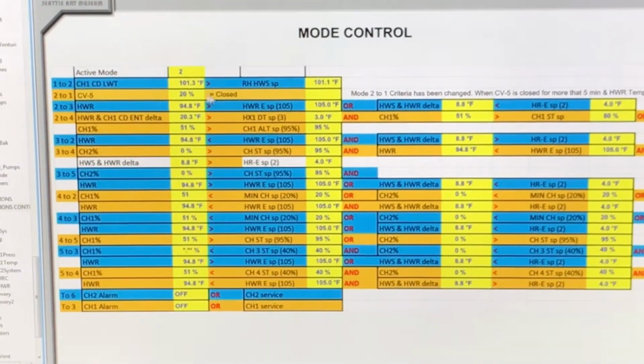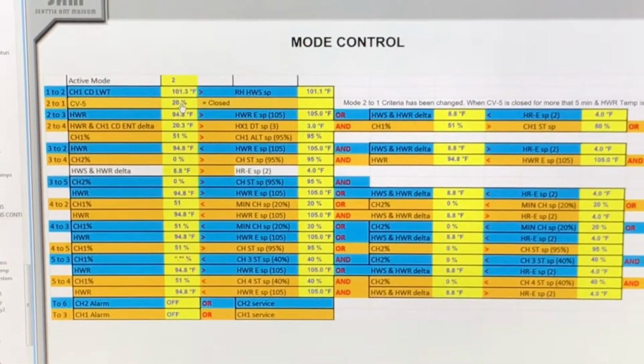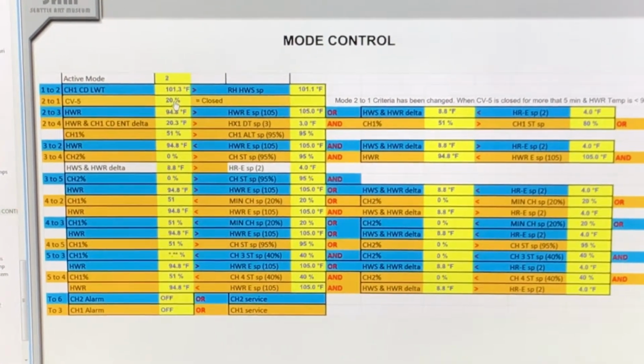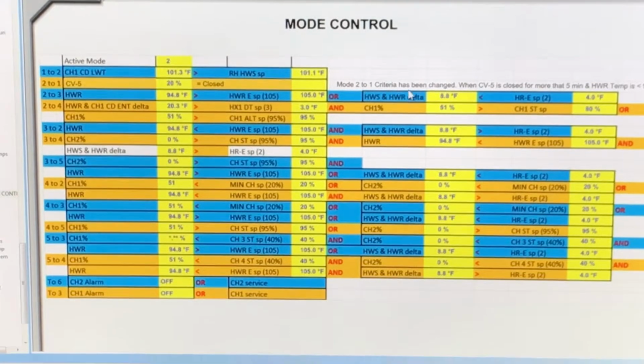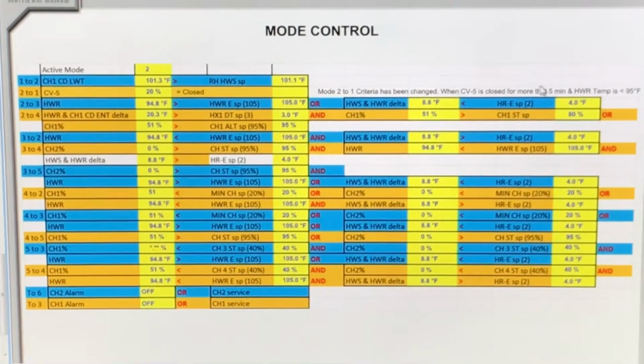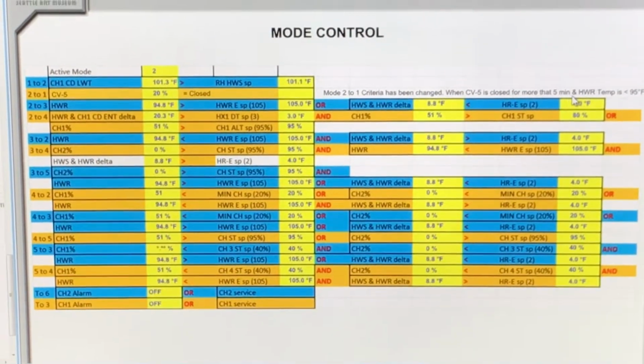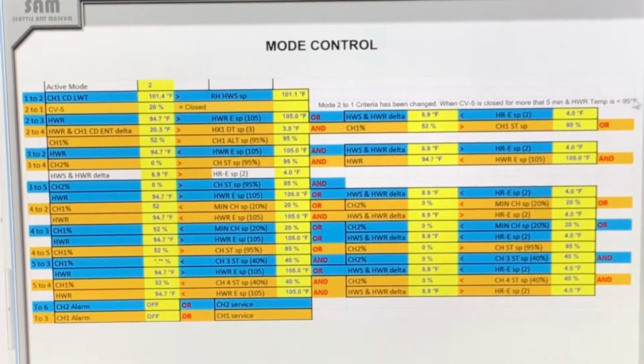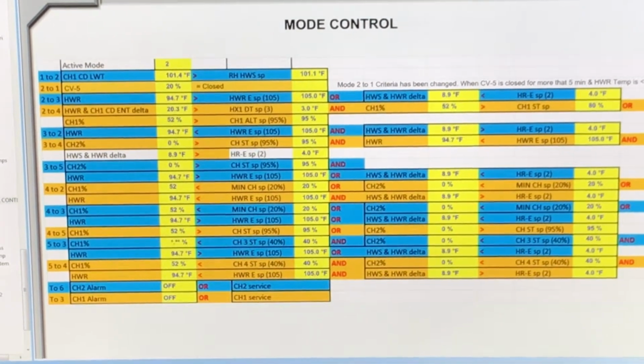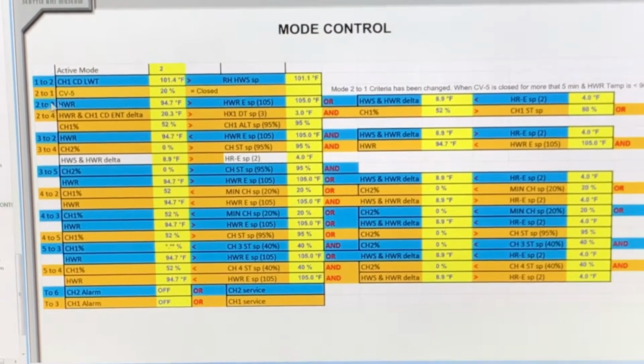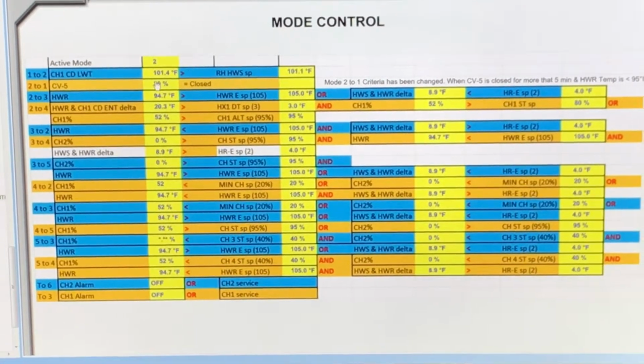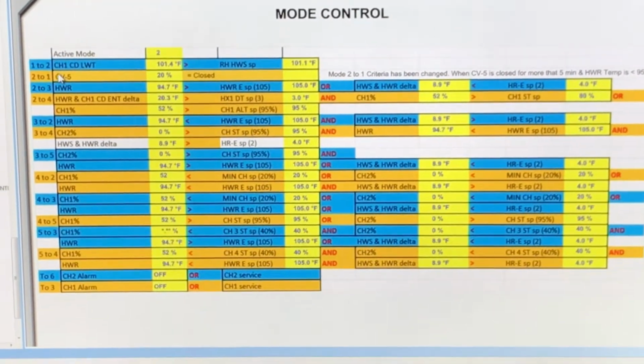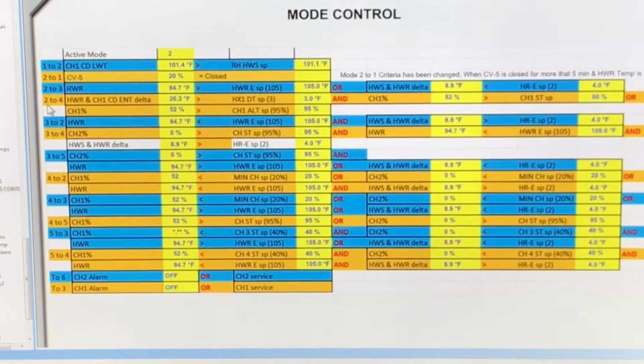CV5 is closed. Well, it's not. And it's closed for a certain amount of time too, isn't that correct? The mode 2 to 1 criteria is when it is closed for more than 5 minutes and the hot water return temp is less than 95. So that's not going to happen very often, but that is there also, because the temperature is always around.